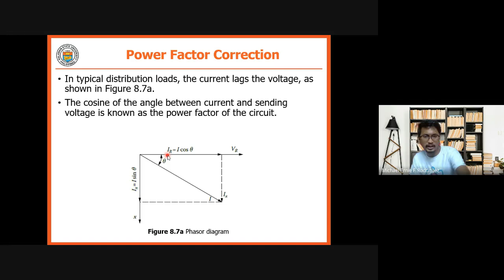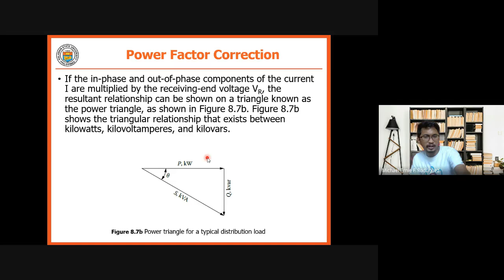So if the in-phase and out-of-phase components of the current I are multiplied by the receiving end voltage VR, the resultant relationship can be shown on a triangle in here. So that is the power triangle. The power triangle shows the relationship between your kilowatts, P in kilowatts, your Q, kVAR, and your S, kVA. So that is a power triangle for your typical distribution load.